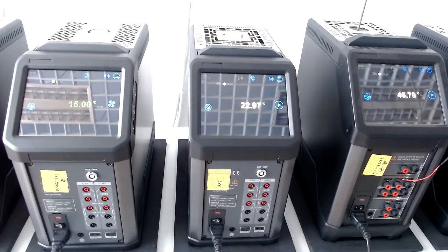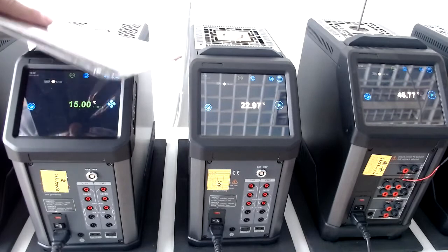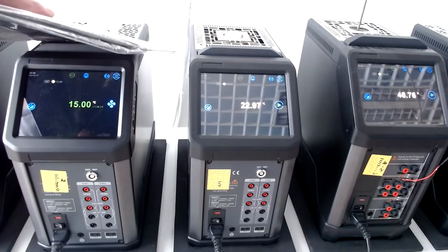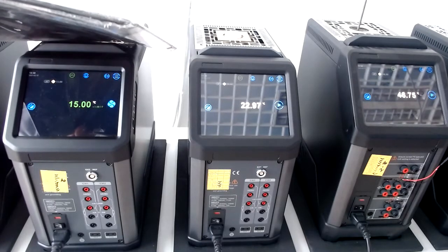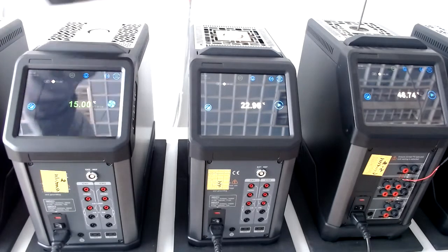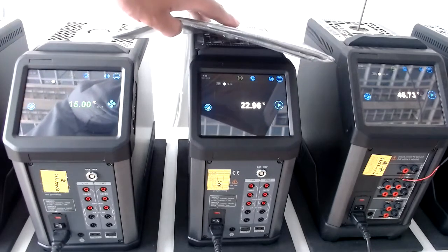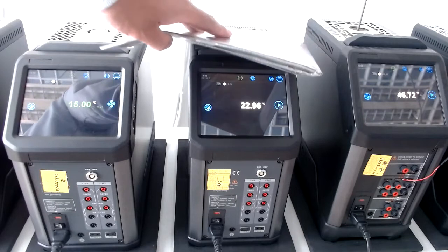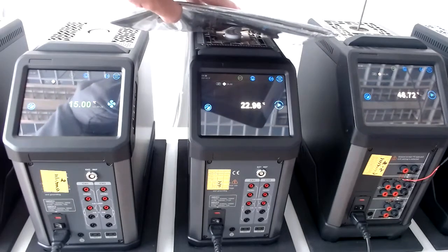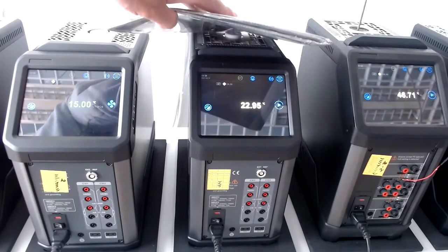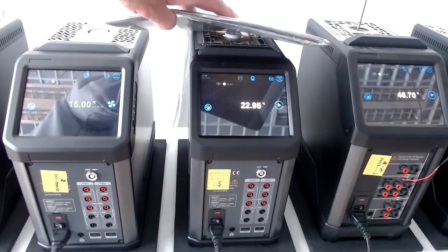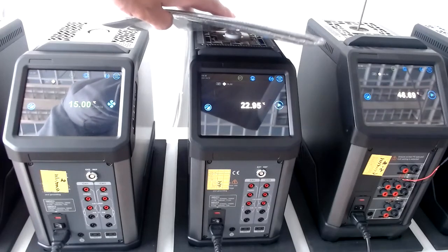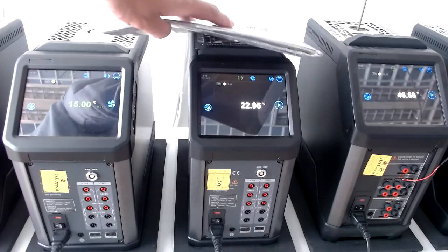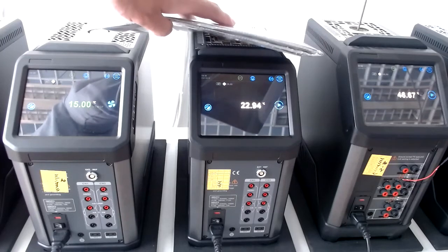Currently I have three devices here. This one is the A75 155, currently at 15 degrees C. This one is the A75 350 model. Because the room temperature is 23 degrees C and the 350 is a high temperature dry well, it cannot reach a temperature below room temperature, so it's currently about 23 degrees C.